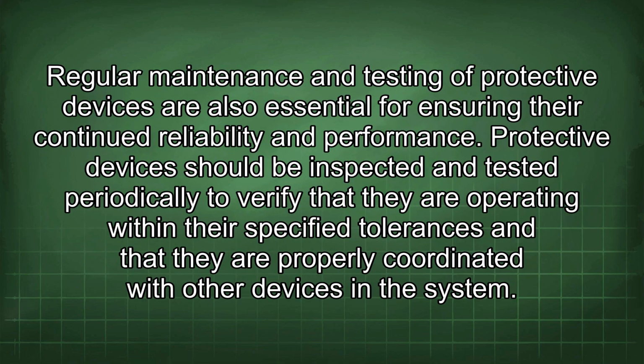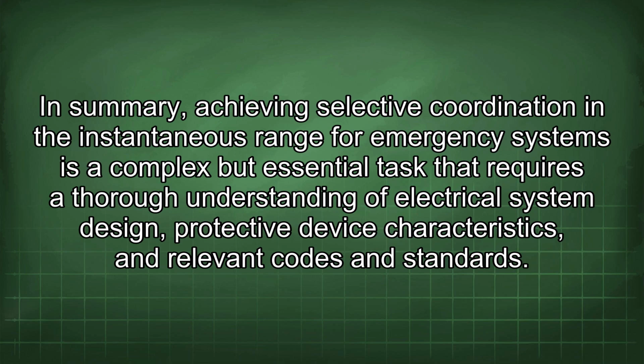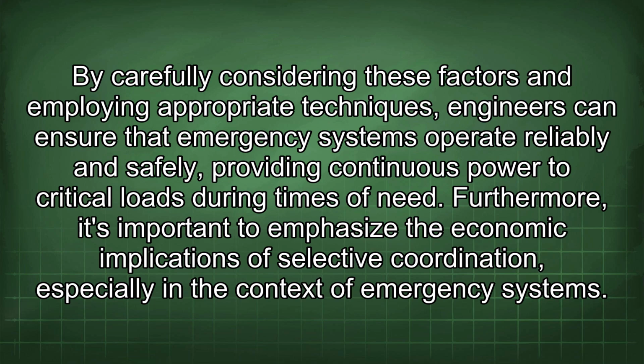Regular maintenance and testing of protective devices are also essential for ensuring their continued reliability and performance. Protective devices should be inspected and tested periodically to verify that they are operating within their specified tolerances and that they are properly coordinated with other devices in the system. In summary, achieving selective coordination in the instantaneous range for emergency systems is a complex but essential task that requires a thorough understanding of electrical system design, protective device characteristics, and relevant codes and standards. By carefully considering these factors and employing appropriate techniques, engineers can ensure that emergency systems operate reliably and safely, providing continuous power to critical loads during times of need.